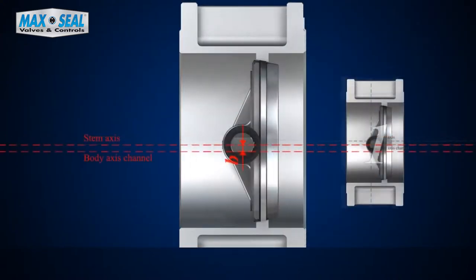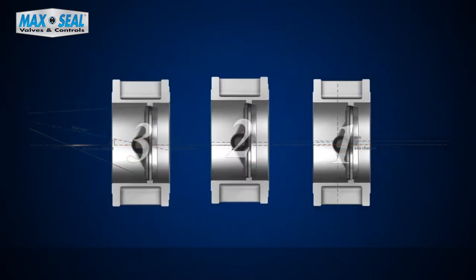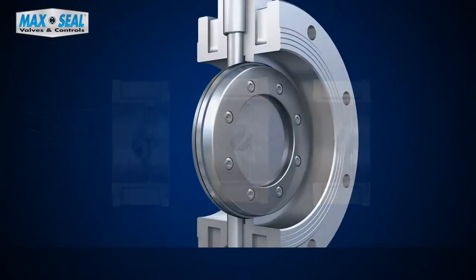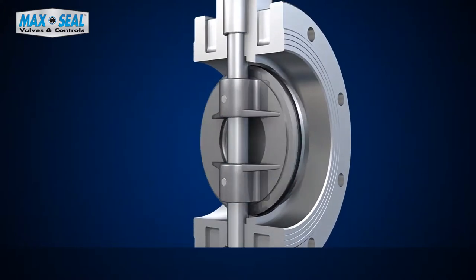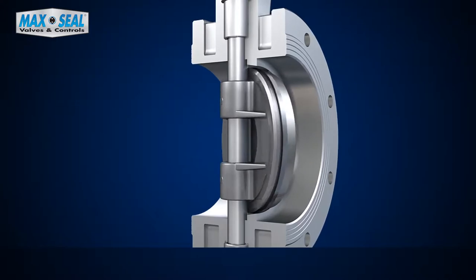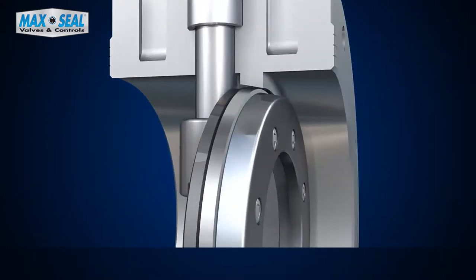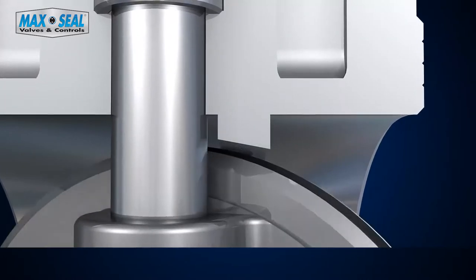5. The butterfly valve adopts the principle of a three-dimensional eccentric design. The valve makes the space trajectory of sealing the surface to achieve an ideal seal, solving the traditional problem in the eccentric butterfly valve opening and closing 0 to 10 degrees. The seal face is still in the sliding contact friction moment.